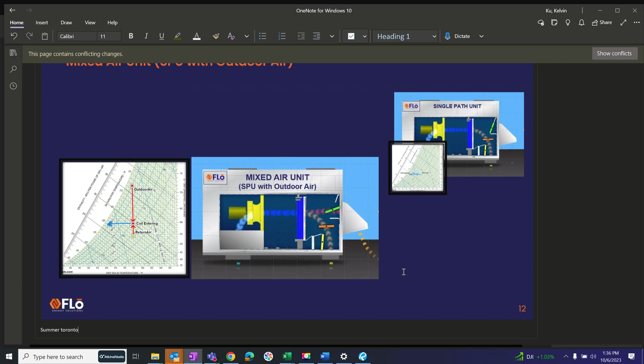What's difficult about this is you have a large volume of air—all the outside air and all the return air going across this one coil. Coils don't perform as well when we don't limit the amount of air over them, especially for dehumidification. We want that air to dwell on the coil so the moisture comes out.